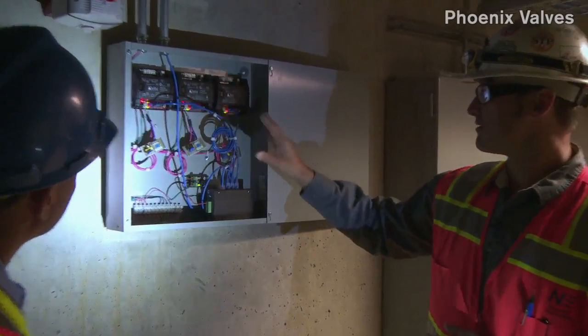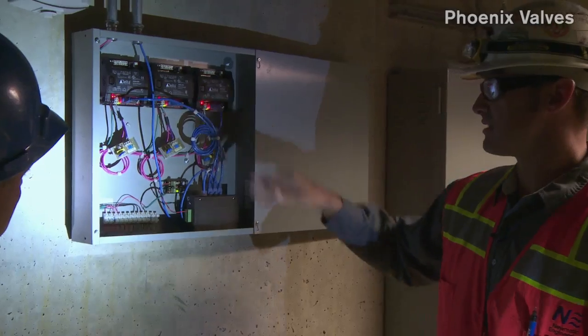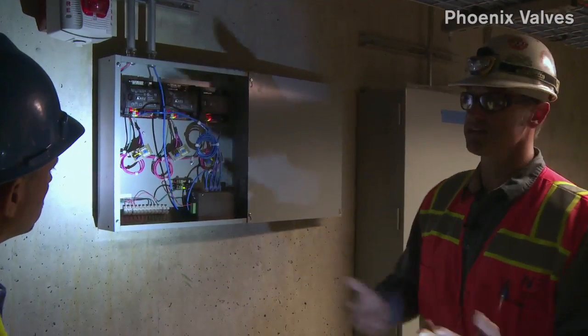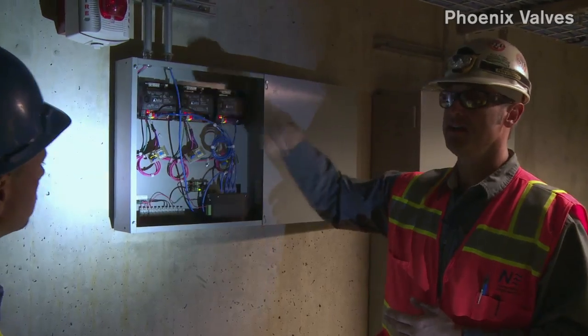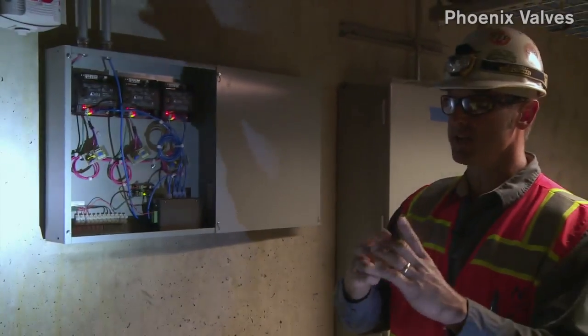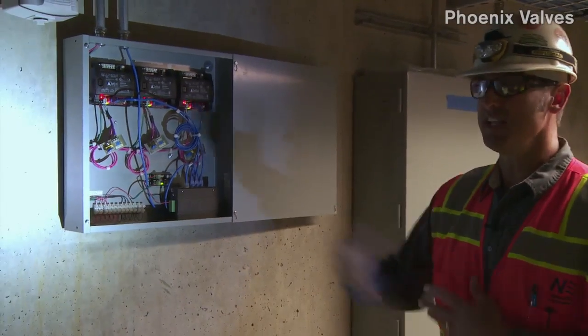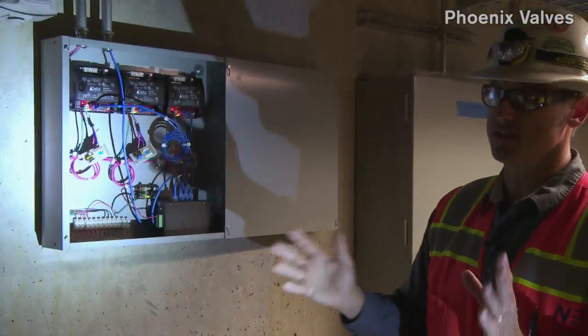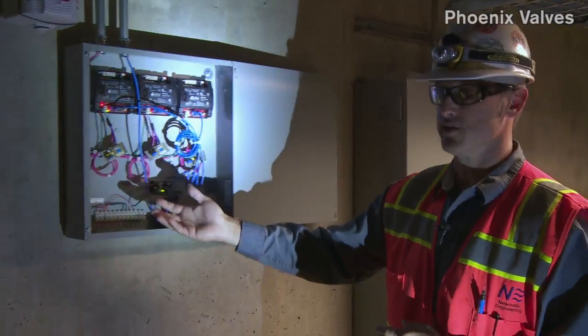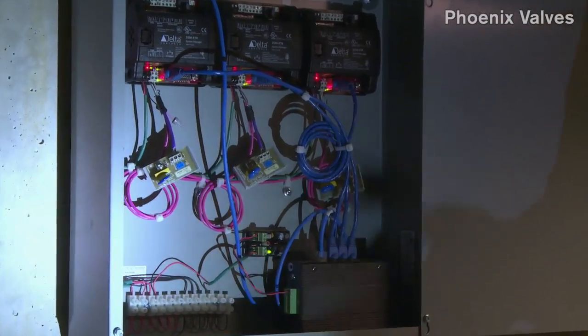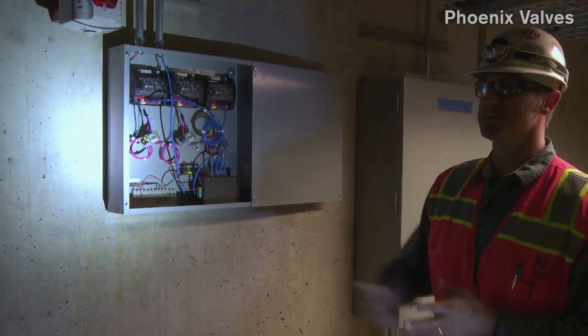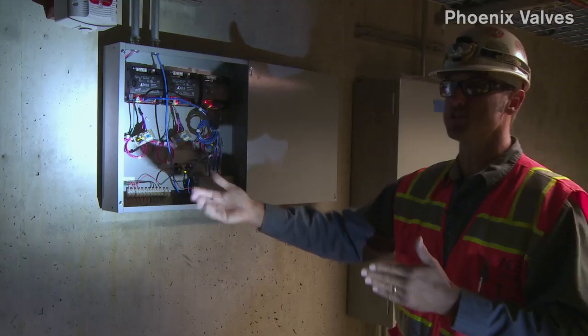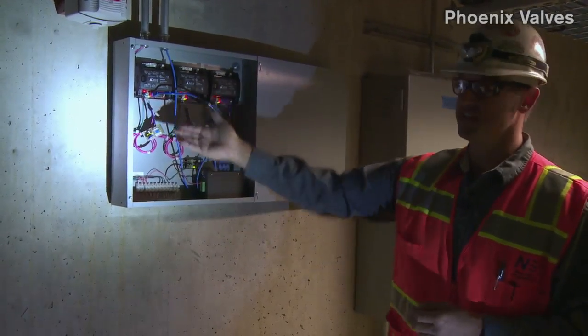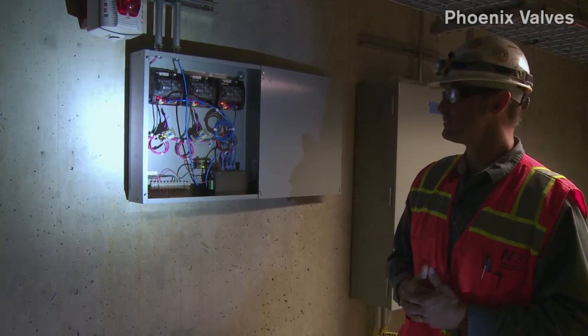But they always say that any type of MSTP system, you always want to put end of lines in. The Johnson Controls has it. Sometimes they have devices that have a built-in end of line. They flip a switch. Sometimes they put in their own end of line wired terminal. Each place usually has its own end of line, and they usually always recommend when they do any troubleshooting, the first thing the place will do that you call up, they'll say, is your wiring good? Do you have end of line terminators on there? If you say no, they'll say, call me back, go put an end of line on all your runs and then call me back. Because they could be troubleshooting for days and the issue might just be that.